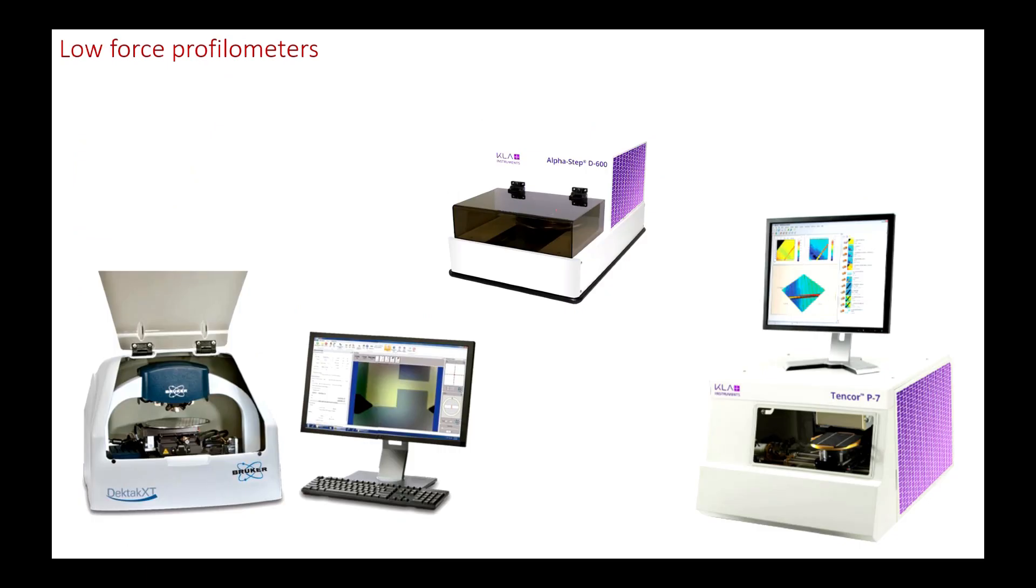Some profilometers are specialized in measuring microelectronic components, even silicon wafers. These very fragile surfaces require an extremely low force of contact, thanks to dynamically controlled force. Models intended for microelectronic component production lines in a clean room can receive closed cassettes that contain several wafers, which are loaded and unloaded in the profilometer automatically.